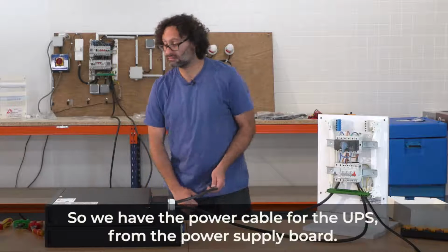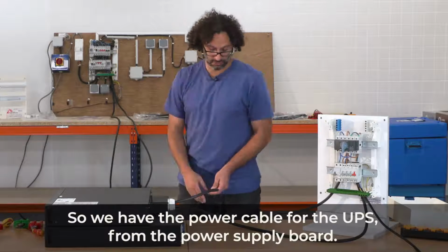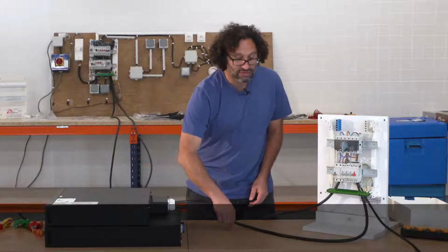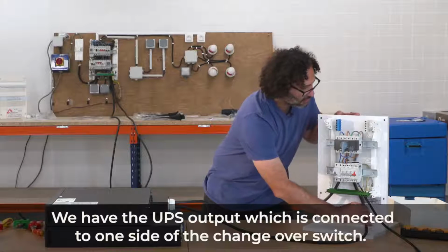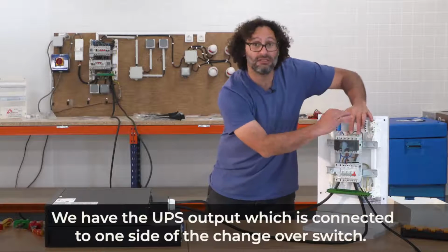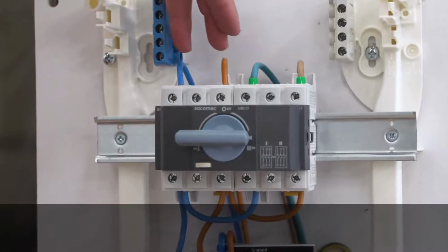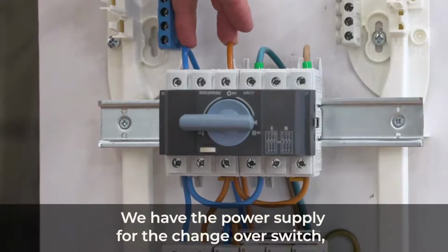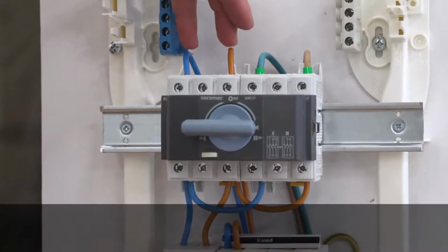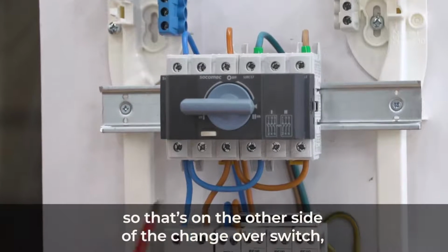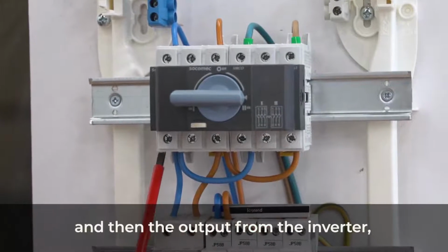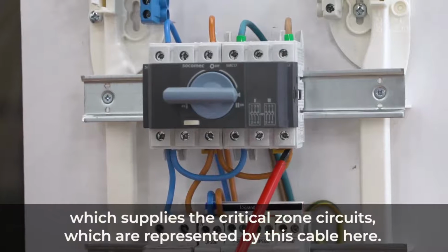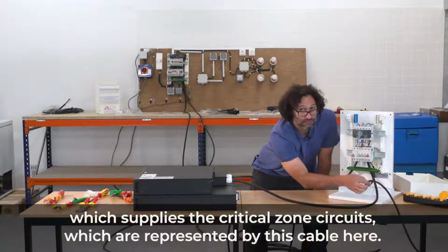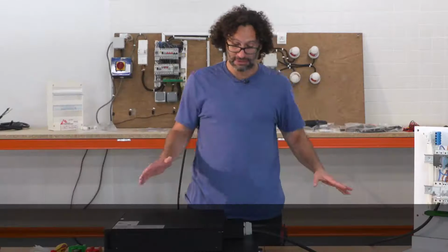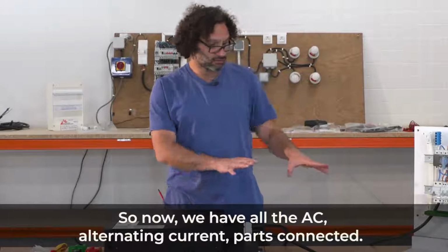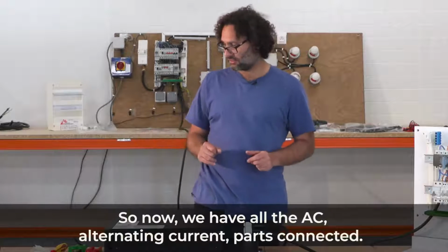So, we have the power cable for the UPS from the power supply board. We have the UPS output, which is connected to one side of the changeover switch. We have the power supply for the changeover switch, so that's on the other side of the changeover switch. And then the output from the inverter, which supplies the critical zone circuits, which are represented by this cable here. So now we have all the AC, alternating current parts connected.